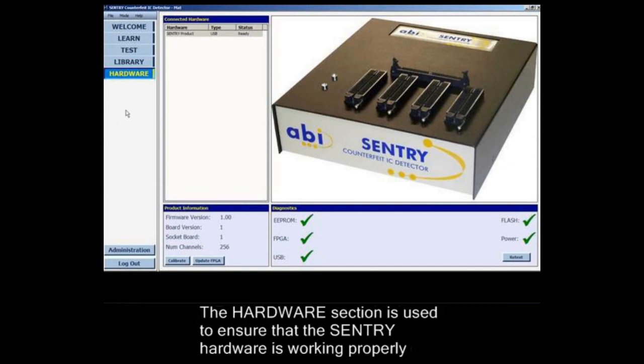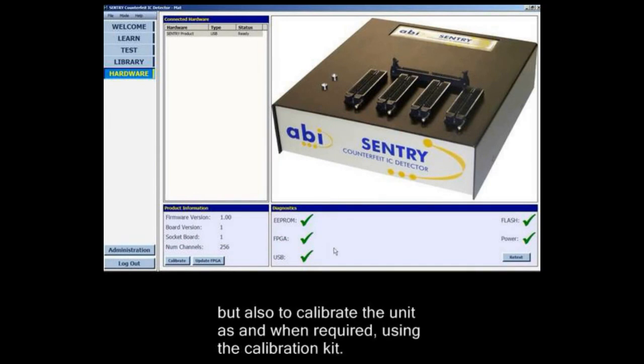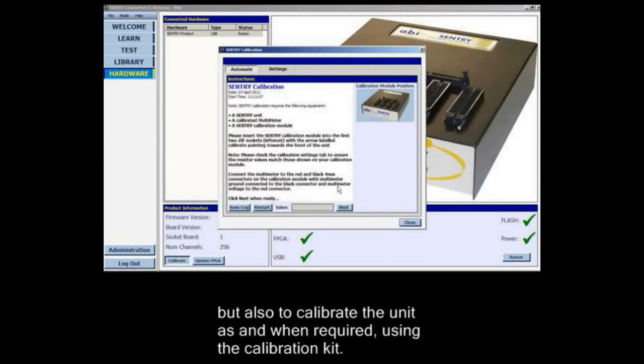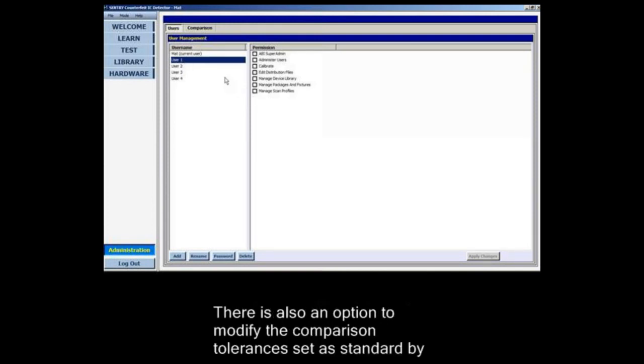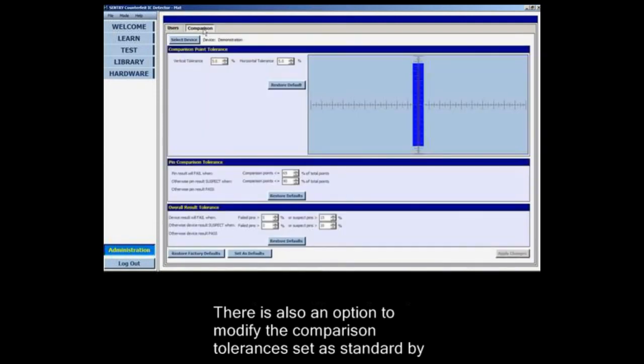The hardware section is used to ensure that the Sentry hardware is working properly, and also to calibrate the unit as and when required using the calibration kit. In the administration section, users can be added or deleted and granted certain access to the software sections. There is also an option to modify the comparison tolerances set as standard by the Sentry software.